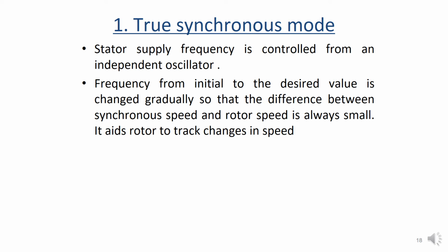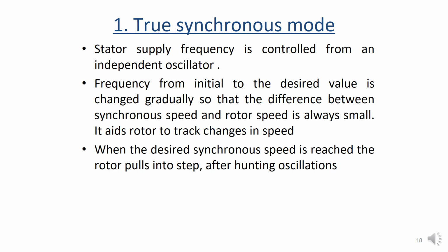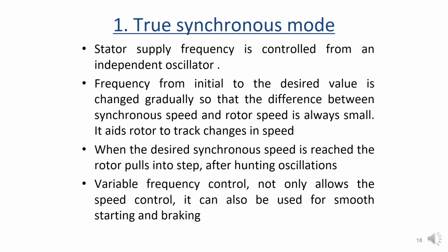The frequency from initial to the desired value is changed gradually so that the difference between synchronous speed and the rotor speed is always small. It aids the rotor to track changes in speed. So when the desired synchronous speed is reached, the rotor pulls into step after hunting oscillations. The variable frequency control not only allows the speed control, it also can be used for smooth starting and braking.